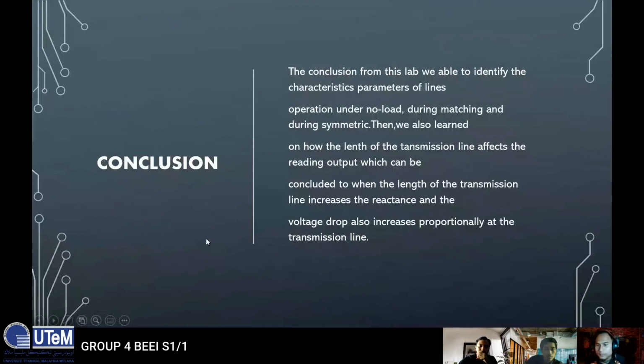For the conclusion, from this lab we were able to identify the characteristic parameters of line operation under no load, during matching and during symmetric. Then we also learned how the length of the transmission line affects the reading output, which can be concluded that when the length of the transmission line increases, the reactance and the voltage drop also increase proportionally.